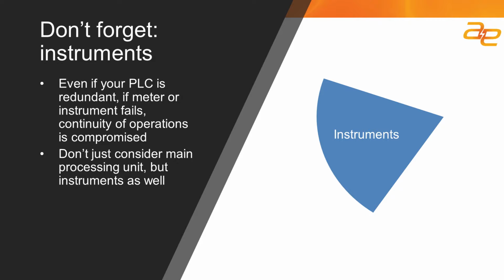And if control of temperature within that room is very critical, you may want to consider not only having one temperature sensor, but maybe having several temperature sensors. So certainly you have to consider your application, and you have to consider what you would do should one of the instruments that's critical towards the control of the process or the equipment or some aspect of the facility fail. And that applies not only to instruments, but also controls that are outside of the primary control system itself, such as motors or pumps or fans, or even electrical switchgear. It could be UPS systems. Again, whatever it is that comprises your control system, you must take into consideration from a holistic view what it is you're trying to achieve at the end of the day, and identify those single points of failure.